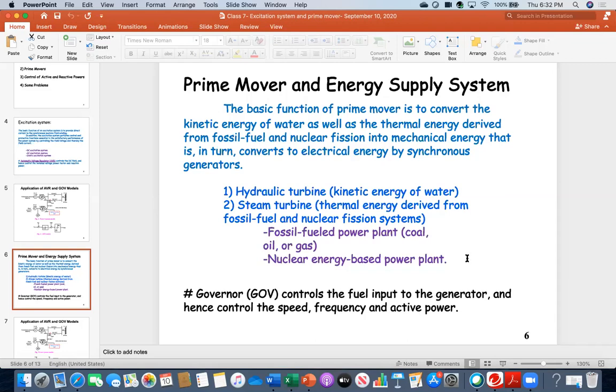How? You all remember the swing equation, Pa equals Pm minus Pe. This means Pe is your electrical output power, active power. If you control that one, then the system will be accelerated or decelerated. And acceleration and deceleration is nothing but the change in speed or frequency. So in that sense, active power control means frequency control, or frequency control means active power control, or speed control means both of these controls. So that's why the governor can control these three variables.